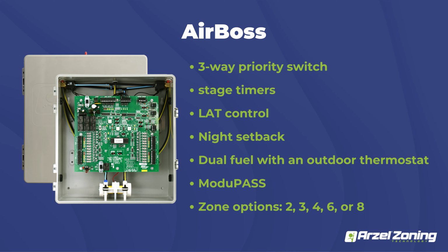This panel will work for anything from single stage conventional all the way through dual fuel applications. If you guys are going to do dual fuel, the only additional component you would need would be an outdoor thermostat that would close on a temperature fall. And that's going to be your balance point setting from the heat pump to whatever your backup heat source is going to be. It's also going to ship with our ModuPASS, which if you guys aren't familiar is our modulating bypass, which we'll cover a little bit later as well. So it's just a much better bypass than your standard barometrics would be, and we'll cover that.